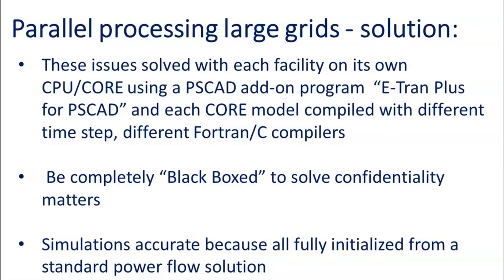For example, if you've got a wind turbine coming in that's got sensitive controls in it, the supplier doesn't want the program to be known, what's inside it. So they'll send it to us black boxed based on a non-disclosure agreement, and that's put on its own core. That helps solve the confidentiality matters. But the simulations are accurately initialized from a power flow solution, the standard power flow solution, which is a great help.